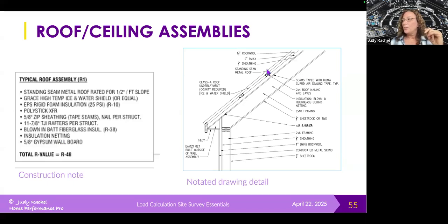You could also end up with a notated drawing like this one, where I'm getting all the different layers. On this one, I'm being told it's 1.5 inches of rock wool. So this is where I need to go back to the person and say, I think rock wool is typically X per R value per inch, but what are you thinking you're getting? We need to be in alignment, in agreement, about what I'm thinking that type of insulation's R value actually is versus what you're thinking you're actually going to put on this house.